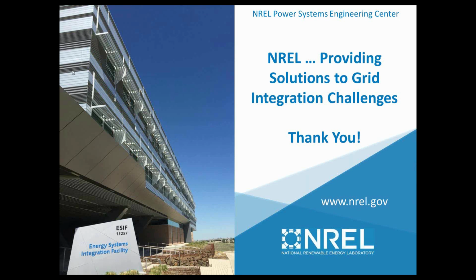Obviously, things like Sandia voltage shift and Sandia frequency shift are out in the public domain and are used. I think some of the other ones that have a lot of patenting around them are just faster acting, if you will. But as far as I know, if you implement all of these, you will still be able to meet the requirements. The problem is that you can't really guarantee or assume you know what each of the manufacturers are doing. The only thing you can do is if they meet 1547 or UL 1741, they've gone through a fairly rigorous test that's really trying to trick the inverter into an island condition.